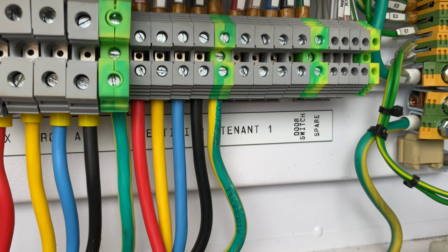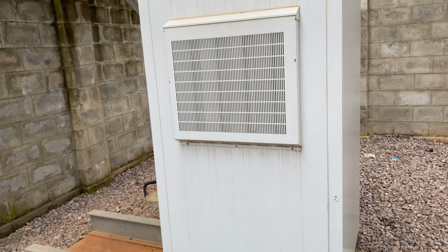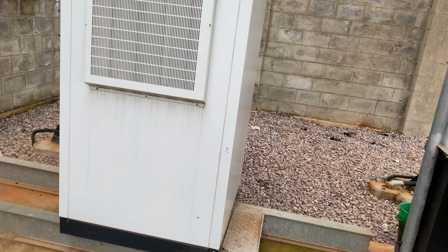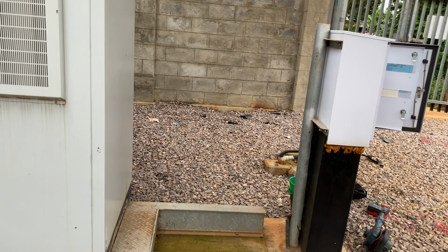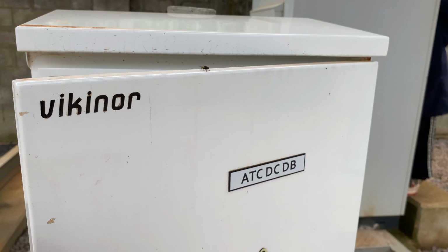I assume they think the power is from the ATS, and behind it goes to the rectifiers. These wires go to the rectifier, and that is the rectifier, this bigger thing, and you will always find this bigger cabinet on a telecom site. So from the rectifier cabinet, that AC is always converted from AC to DC negative 48, and then it goes to this DCDB.